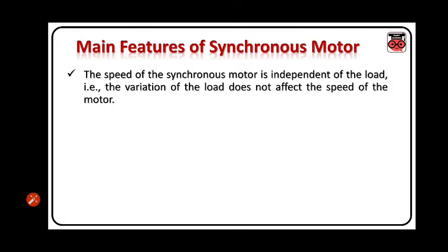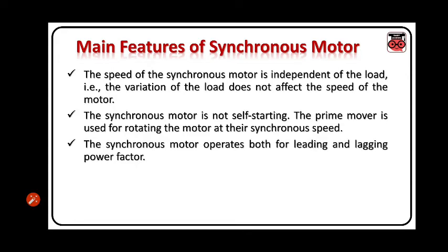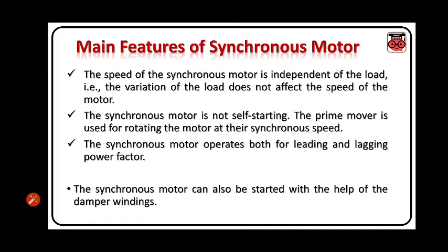Now, the features. The speed of the synchronous motor is independent of the load. So the variation of the load does not affect the speed of the motor. The synchronous motor is not self-starting. The prime mover is used for rotating the motor at the synchronous speed. The synchronous motor operates for both leading and lagging power factor. The synchronous motor can also be started with the help of damper winding.